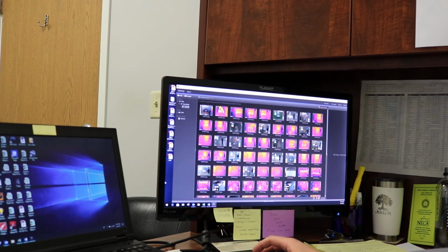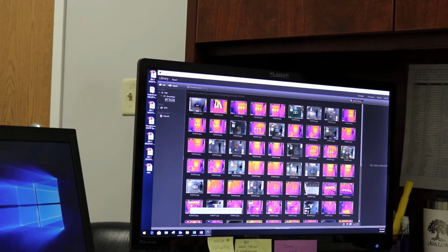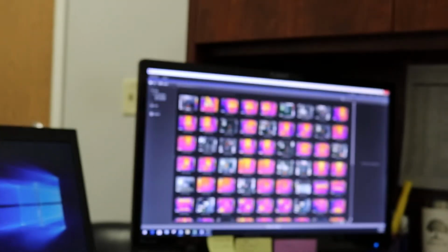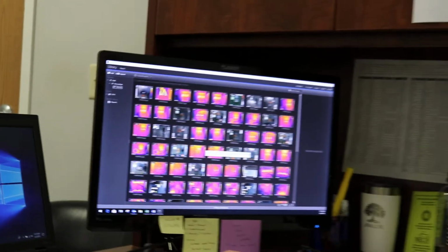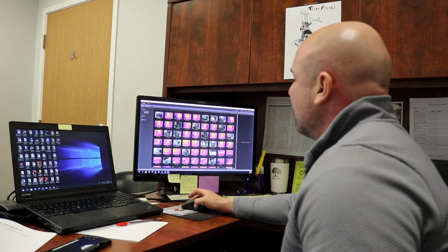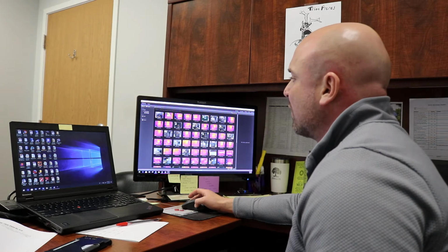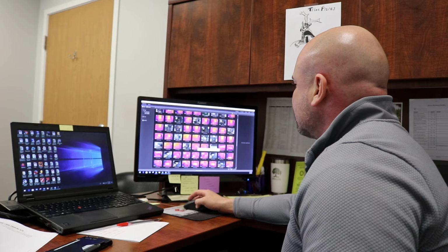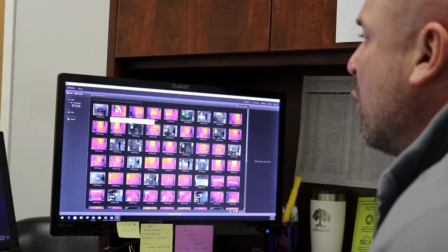Okay. All right. So for this particular customer, we went in and installed a new MCC on a mezzanine level of their plant. Afterwards, we went back in to establish a baseline and shoot all of the terminations that we made throughout the MCC, not only for our own records and security, but to potentially go back at a later date to see if there are any changes or anomalies that might need to be addressed before they fail. So we would go into the software, select each particular one, and open up a new report.